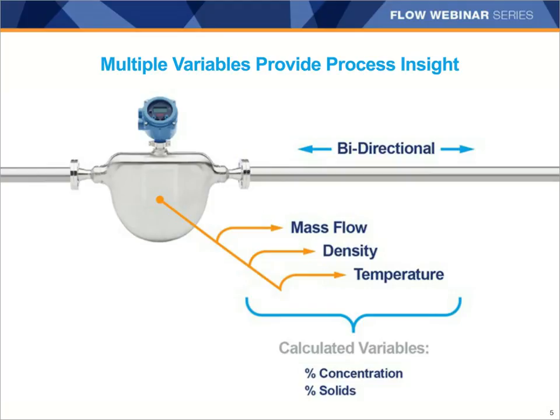So as you can see, there are a lot of process variables that are available to you, and these are available regardless of which direction your material is flowing. So whether you're using your meter for intentionally bidirectional applications like loading and unloading, or if the flow changes directions unintentionally due to a failure of a valve or something of that nature, you have the visibility not only to the flow of the fluid, but you can also see how the fluid is behaving and see some of its properties. That data can be output from the Coriolis meter, and then you get a lot of information just around your process and what's going on, helping you to make more informed decisions.